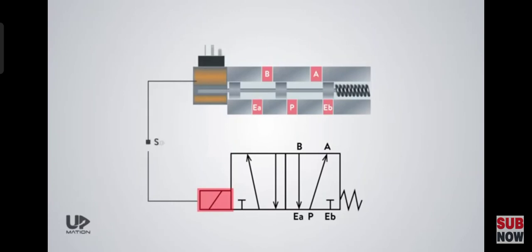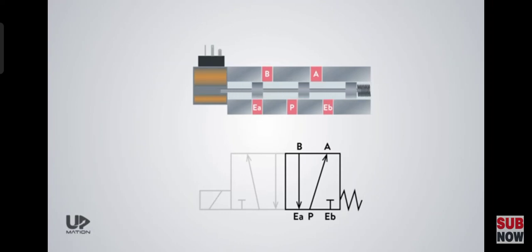This is the sign for the electric solenoid spring return. In our circuit, when the valve is in its rest position, this square is active. When the solenoid gets energized and the spool changes position, the other one is active. Generally, the square just beside the solenoid sign is active when the solenoid is energized. And this is a rule of thumb for any directional control valve schematic.